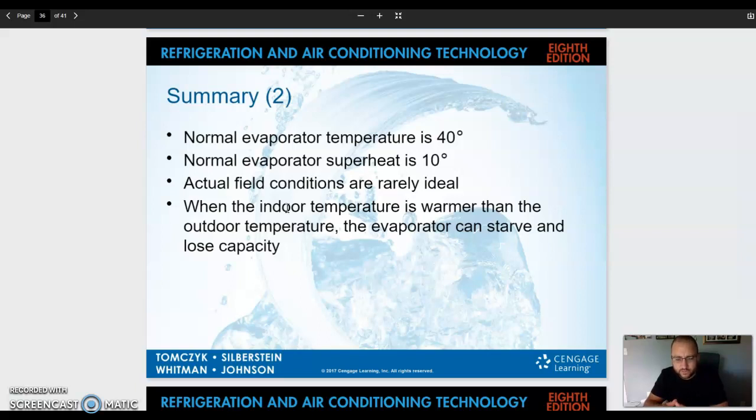So I always start with pressures, temperatures to make sure that I'm close, because I've seen people that start with superheat subcooling, but their pressures, temperatures are way out of whack. You're using those initial temperature readings and pressure readings to make sure that you're close, and then you use superheat subcooling to determine the tweaks, the fine line, between overcharge, undercharge, overfeeding, starved, and all that stuff. So don't start with superheat subcooling. Start with your pressures, your temperatures.